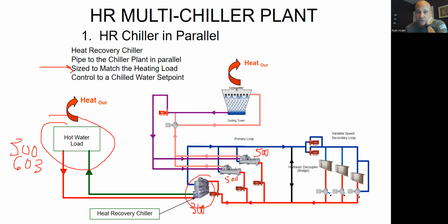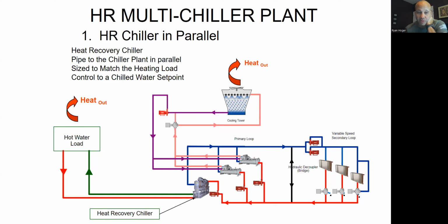When I control this system, I'm going to control this for chilled water. What does that mean? That means somewhere in here, I have to put a temperature sensor in the water piping that says how much to ramp this chiller up and down. It's going to be variable capacity like everything else is. So somewhere in here, I'm going to put a temperature sensor, in this case on the chilled water side, and I'm going to say, hey, dude, make me 44-degree water. And whatever heat you have, instead of sending it to the cooling tower like these dudes do, you're going to send it over here to this heat exchanger. It's going to heat up this boiler water or whatever it's going to be.